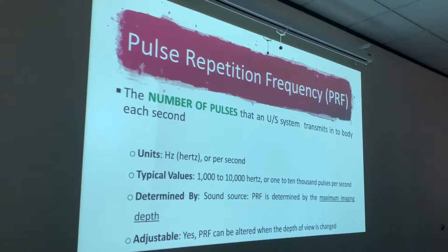All right. So just like the PRP, the PRF is also determined by the source initially, because it's already determined with different transducers. But just like the PRP, because they're inversely related, when we change the imaging depth, we're also changing the pulse repetition frequency.